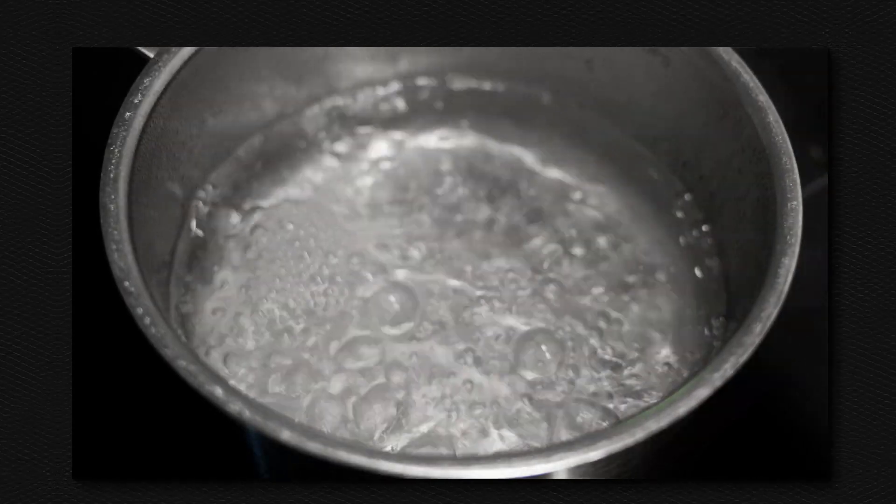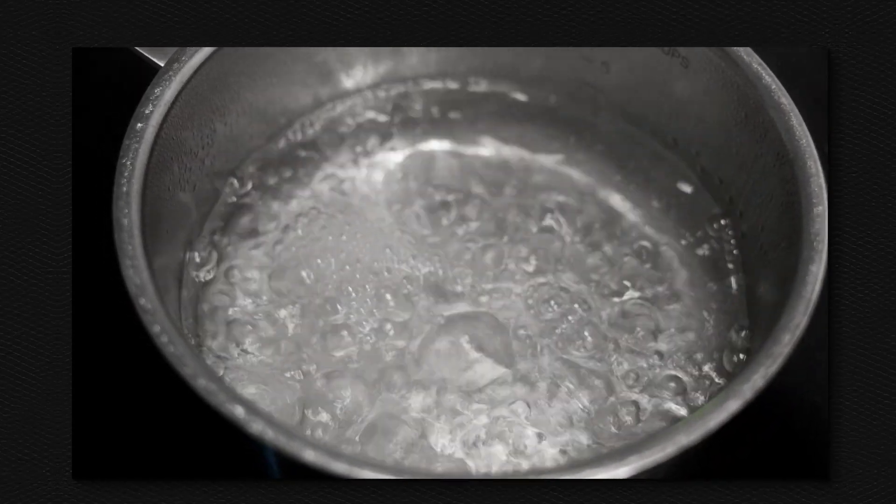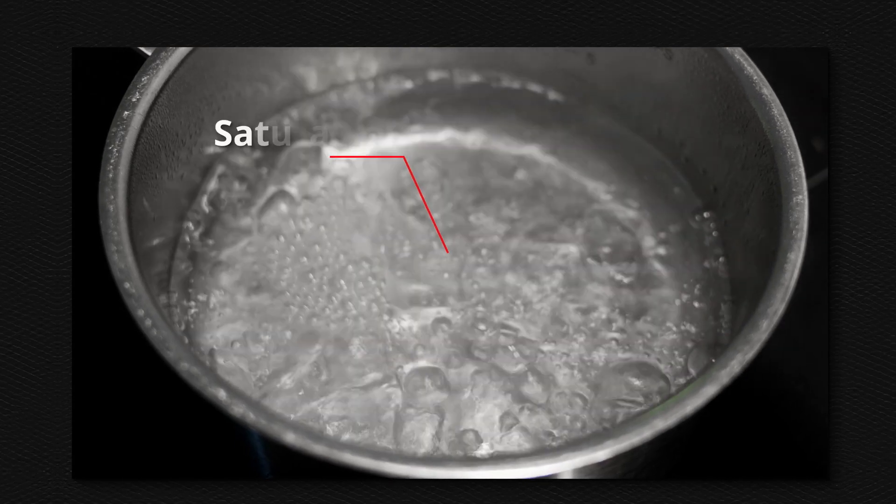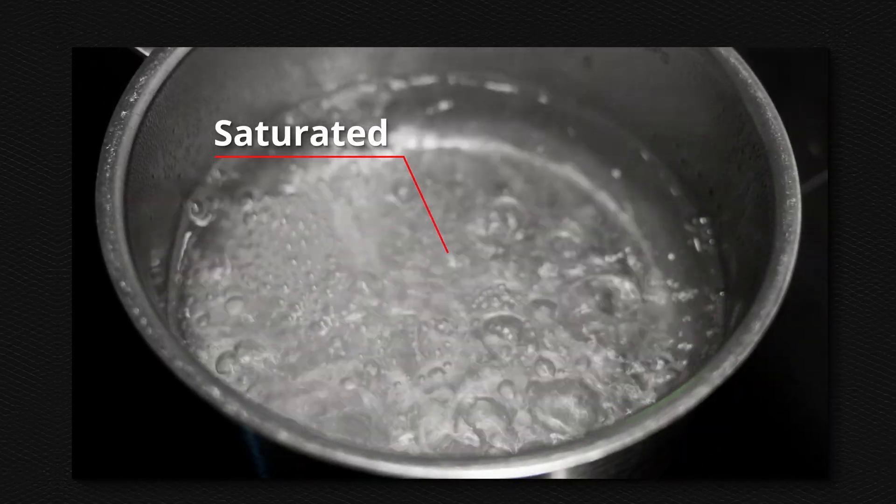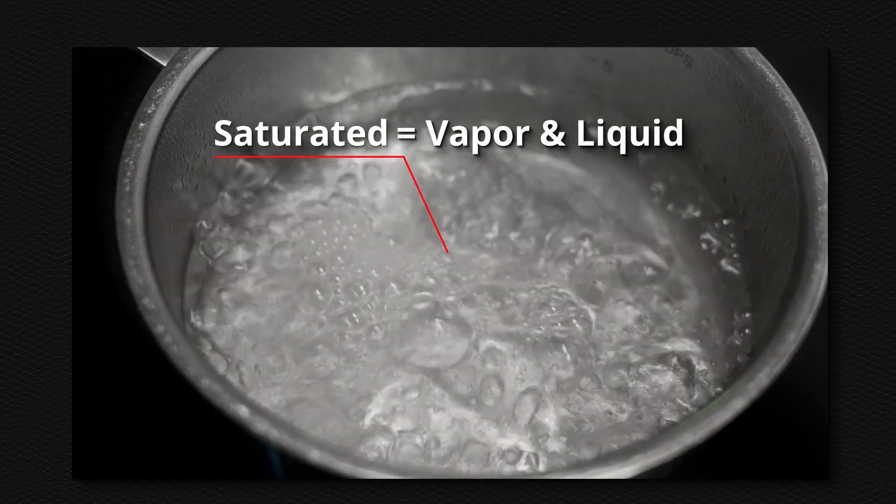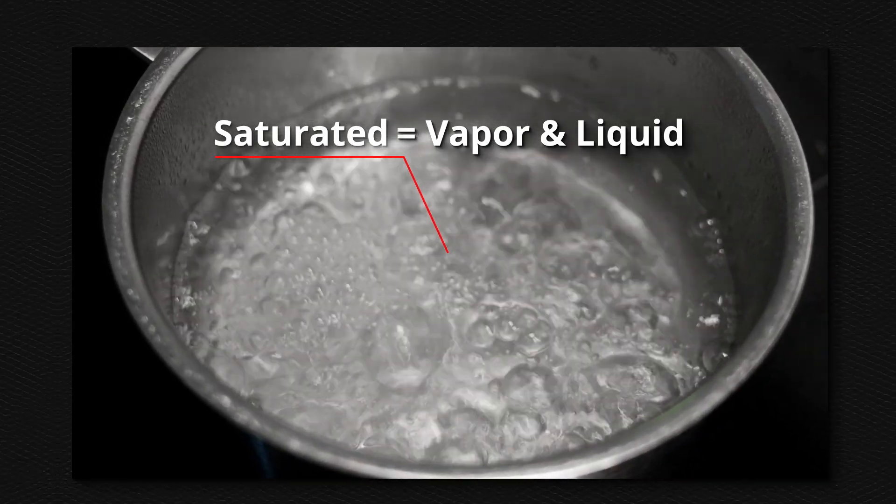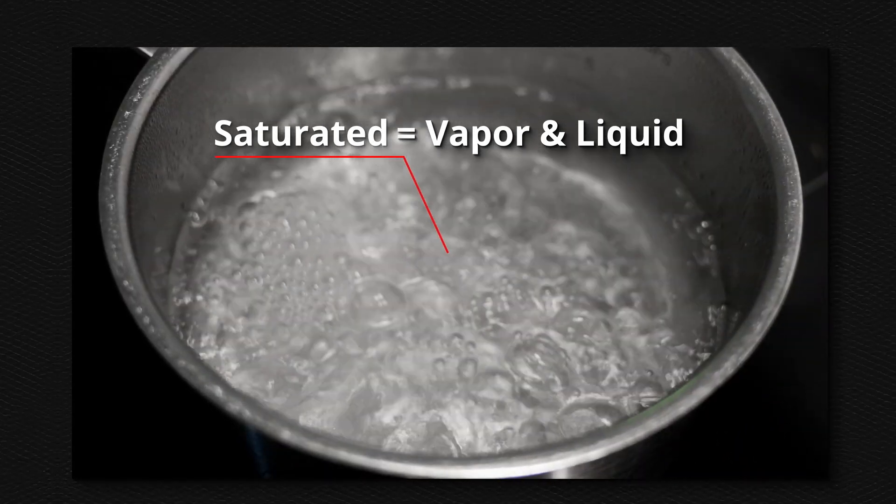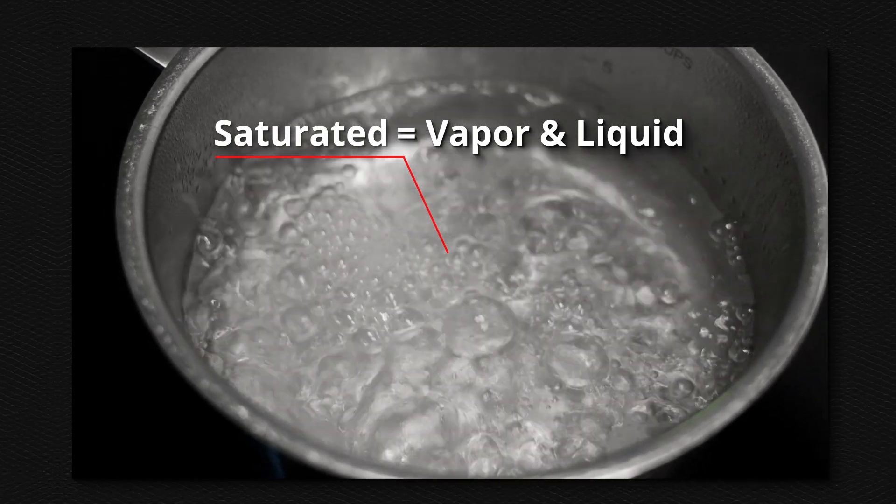Boiling water can help understand the concept of saturated refrigerant remaining at constant temperature. When refrigerant is saturated, in other words, liquid and vapor exist, the temperature will be constant when heat is added or removed. The boiling water is saturated since water and vapor exist at the same time.